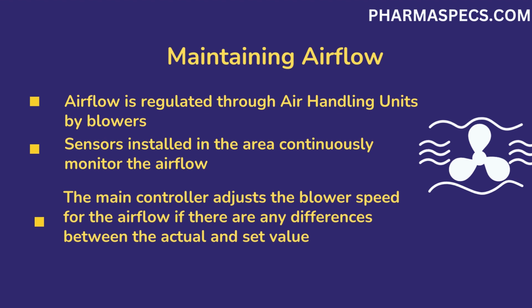Blowers in AHU serve this purpose by generating the required amount of airflow. Sensors installed in the area constantly monitor the airflow and send a value to the main controller. The main controller compares the required airflow with the set value. It increases or decreases the blower speed to compensate for the difference. Airflow depends upon blower speed. The higher the blower speed, the higher is the airflow. Similarly, lower the blower speed, lower is the resultant airflow.